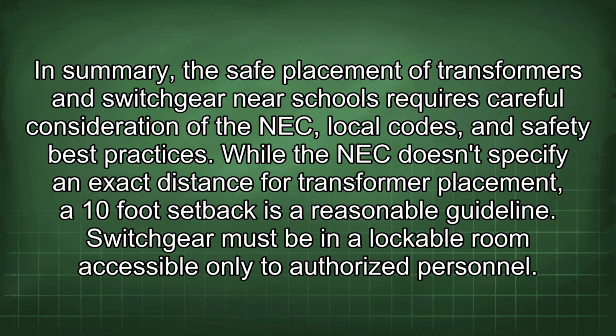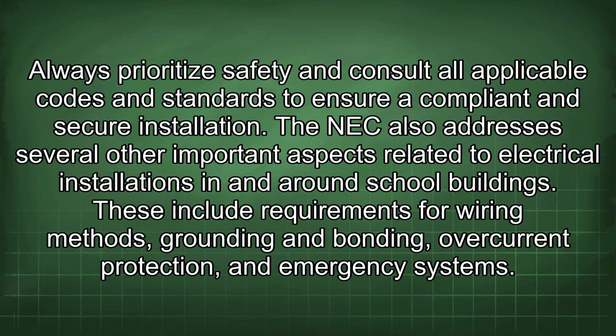In summary, the safe placement of transformers and switchgear near schools requires careful consideration of the NEC, local codes, and safety best practices. While the NEC doesn't specify an exact distance for transformer placement, a 10-foot setback is a reasonable guideline. Switchgear must be in a lockable room accessible only to authorized personnel. Always prioritize safety and consult all applicable codes and standards to ensure compliant and secure installation.